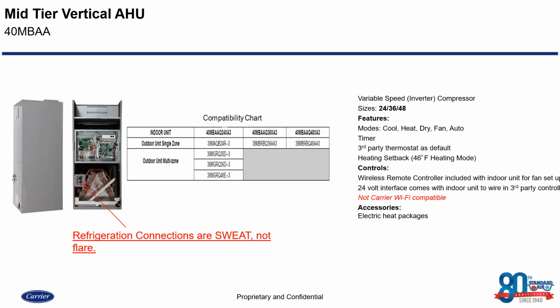Now, with controls for this, we have a wireless remote controller, as I stated before, that is included with the indoor unit for fan speed setup. And we have our built-in 24-volt interface, which is going to allow an integration of a third-party thermostat. And most importantly to note on here, the carrier Wi-Fi option is not compatible with this 40 MBAA.